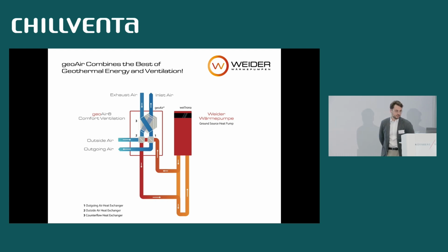The geoAir is a central ventilation system and combines the best of two worlds from ventilation and geothermal energy. On the right, you see the ground source heat pump, our weiTrona, and this can be done with any geothermal source, so probes, trench collectors, source collectors, anything you like. And a part of the brine inside of the collector is going through the ventilation system itself. So on the left side, you see the geoAir, the actual ventilation system.